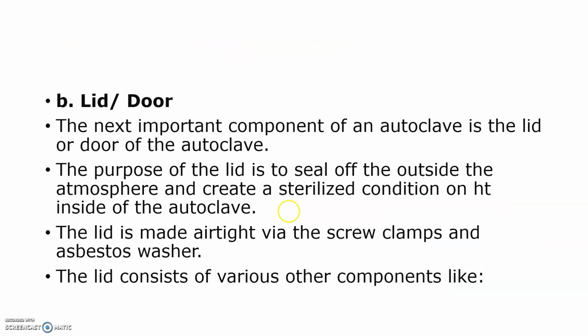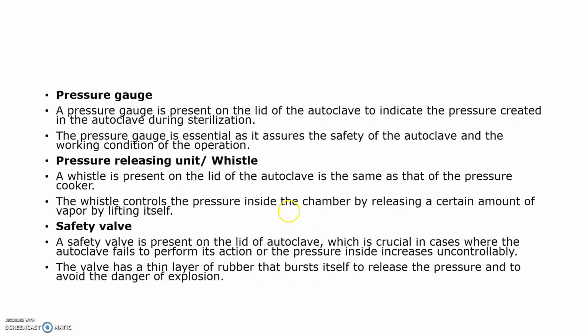Second one is the lid or door. The next important component of the autoclave is the lid or the door. The purpose of this lid is to seal off the outside atmosphere and create a sterilized condition inside. The lid is made airtight through screw clamps and an asbestos washer. And the lid consists of various components like the pressure gauge, pressure releasing unit or whistle, and safety valve. Detailed descriptions are given about the pressure gauge, pressure releasing unit or whistle, and safety valve.